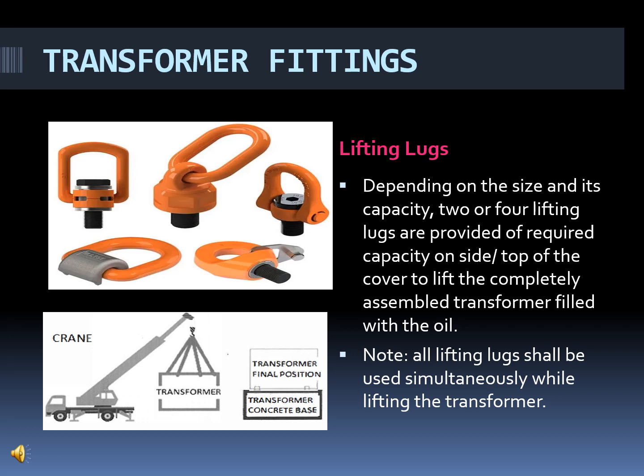Now fitting number 4 is the lifting lugs. I have enclosed the image of lifting lugs and how the transformer is lifted through the lifting lugs using a crane. Just see the brief description. Depending upon the size and capacity, every transformer has 2 or 4 lifting lugs, mounted either on the side or on top of the cover, to lift the complete assembly including the oil-filled transformer. Please note that all lifting lugs shall be used simultaneously while lifting the transformer.